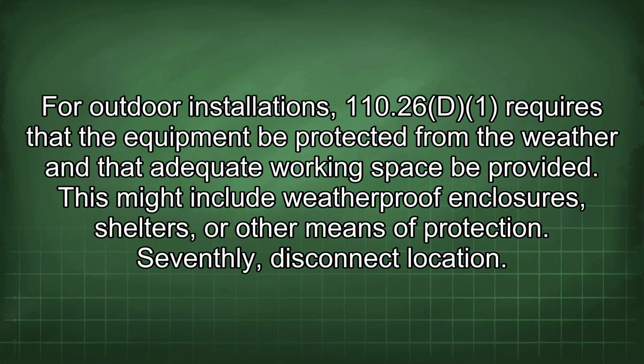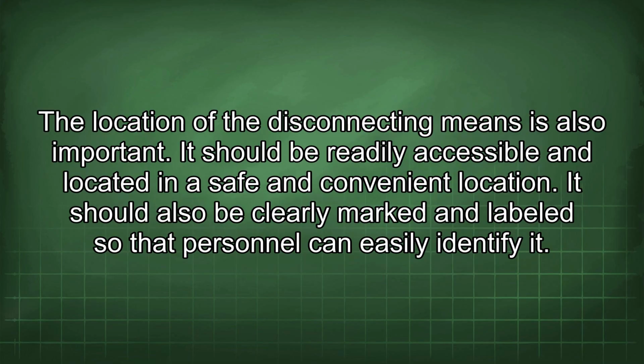For outdoor installations, 110.26 requires that the equipment be protected from the weather and that adequate working space be provided. This might include weatherproof enclosures, shelters, or other means of protection. Seventhly, disconnect location. The location of the disconnecting means is also important. It should be readily accessible and located in a safe and convenient location. It should also be clearly marked and labeled so that personnel can easily identify it.